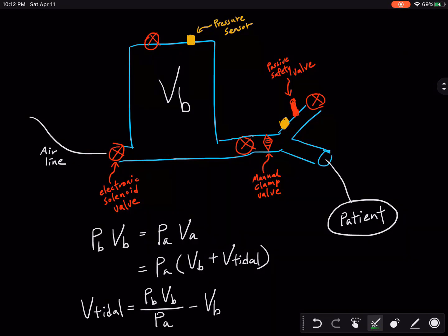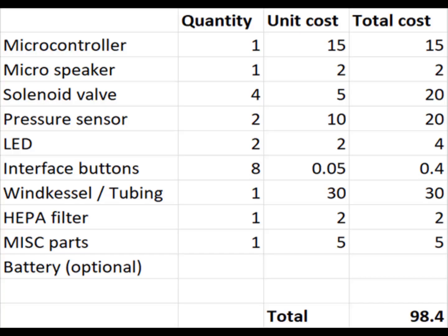compared to many other low-cost ventilator designs involving mechanically squeezing a bag. This is the entire parts list. The construction is very simple. Most of the complexity in this design is in the control algorithm, which once it is developed can be directly uploaded into the microcontroller. Since the electrical power requirement of the design is very low, if needed, the device will be able to operate on battery for many hours.